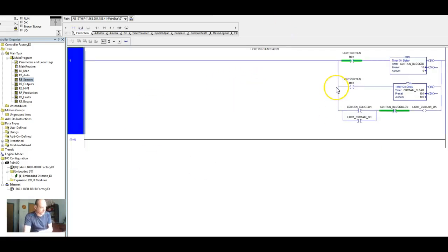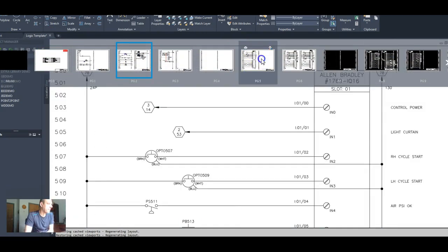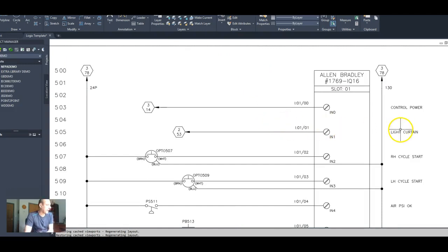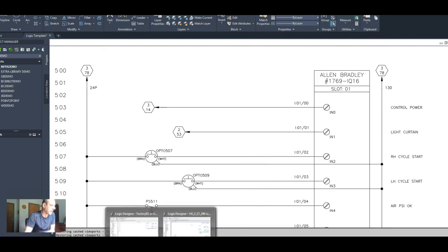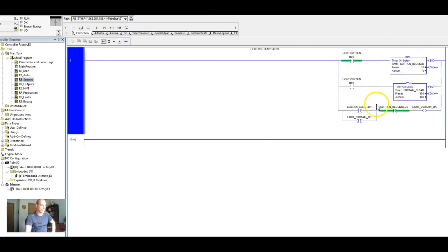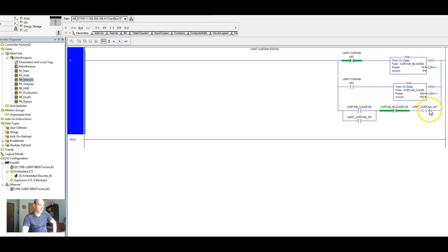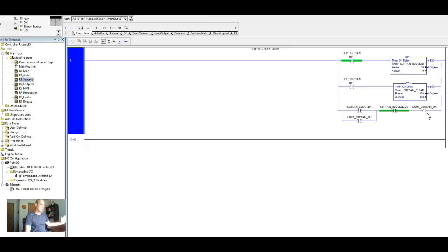So we have our rung. So essentially 101. So if we look back in our circuit, on page five, what we have is light curtains. If that's okay, it's coming into the PLC telling us that it's okay. So now what we have here is light curtain is okay. Our timer is done. If the curtain's not blocked, then we'll get a light curtain okay. We'll write a one to this instruction here, and then we will seal that in. Down here we'll write a one here and we'll have our circuit will be continuous, but we'll be sending a signal to our PLC that the light curtain is okay. Perfect.